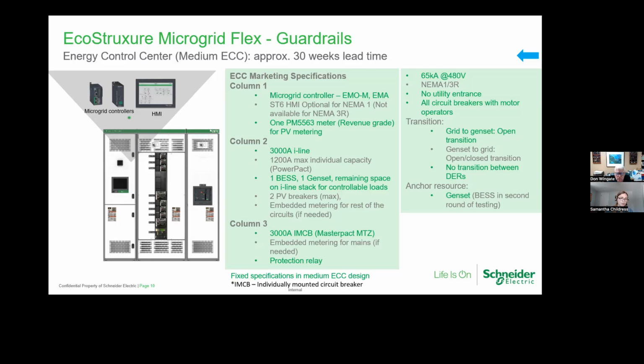So there are 3,000 amps of section in there that you can stack your load breakers, your generation breakers, and that means you can have up to 500 kilowatts or so of a battery.